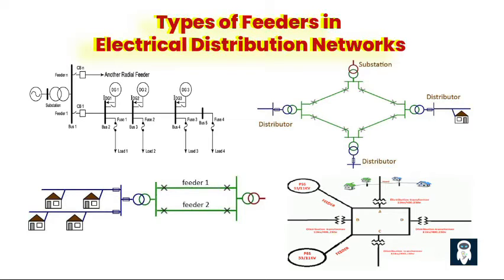Fifth, a double-ended feeder involves connecting two or more sources to a common feeder, providing redundancy and improved reliability. If one source fails or requires maintenance, the load can be seamlessly transferred to the other source, minimizing disruptions. Sixth, the radial ring feeder combines characteristics of both radial and ring main feeders, primarily operating in a radial configuration but incorporating a ring main at strategic points, providing redundancy and alternate paths while maintaining the simplicity of a radial feeder.